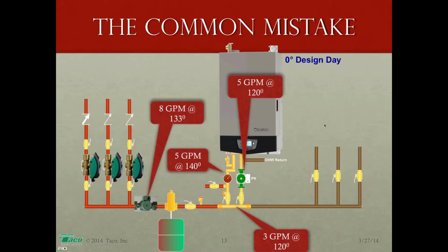All right. Now, here is a common mistake. I want to share this with you guys. This is a very common mistake we see out here. If you set the boiler to make 140 degree water, because that's what you need, and you pipe it up in this manner, if we look at the math, we have 8 gallons of 120 degree water coming back, 5 gallons of 120 going into the boiler, 5 gallons of 140 coming out, mixing with 3 gallons of 120. Really what we're going to have is 8 gallons of 133. And under design conditions, that's probably not going to get her done.